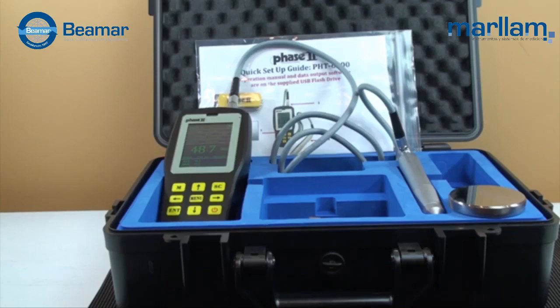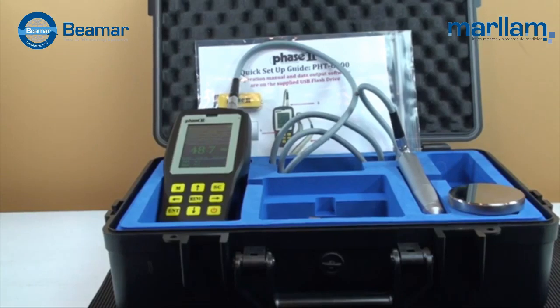It is slower than the dynamic Leeb test, but it also has certain advantages as well. UCI allows for parts down to 80 thousandths thick to be tested, while the dynamic systems could not handle anything less than the mass of 1 inch thick of steel. Maybe the most popular aspect of the UCI hardness tester is that it is classified as non-destructive. It can test hardened parts without leaving a visible indentation mark. This allows for less scrap parts and lower part costs overall.